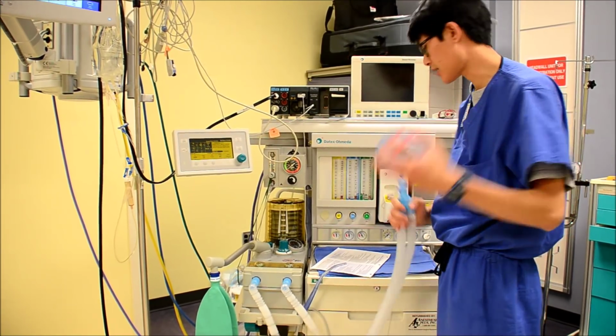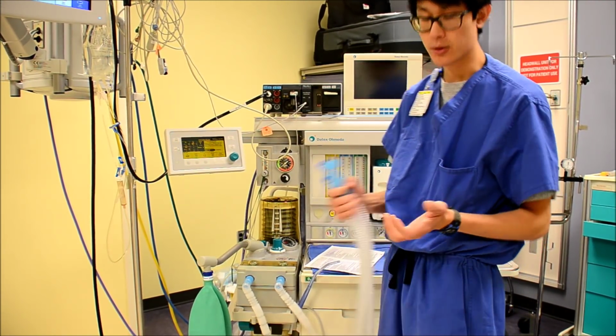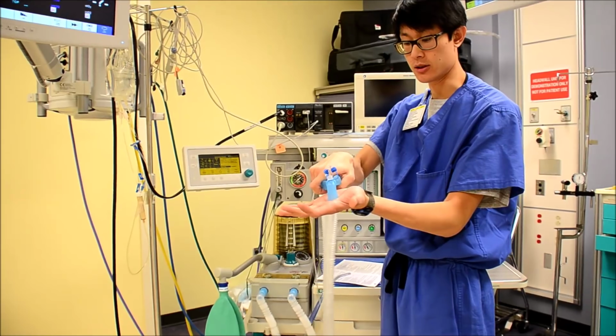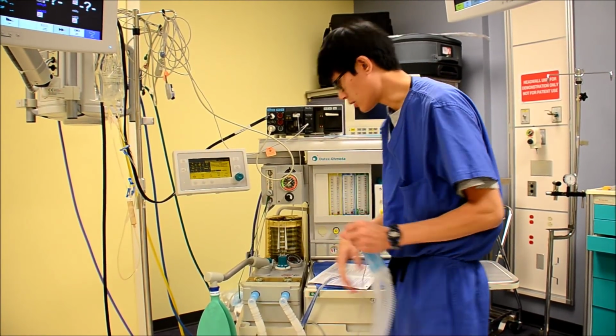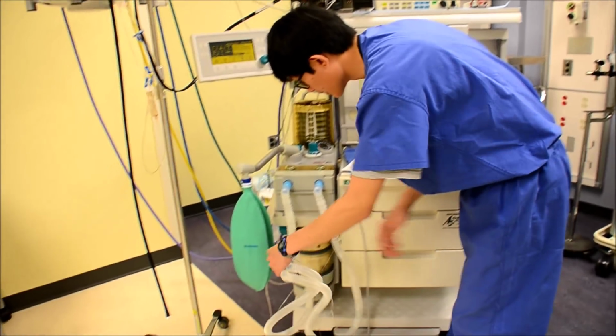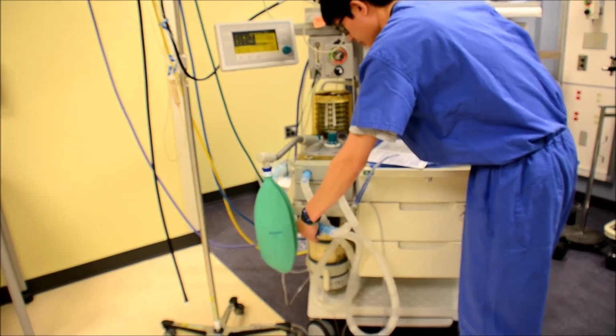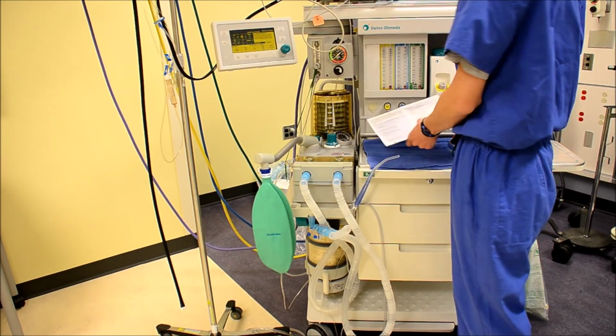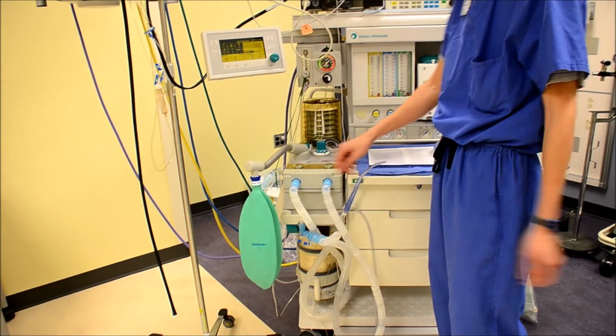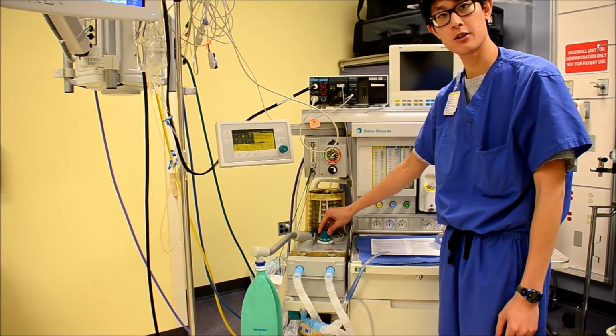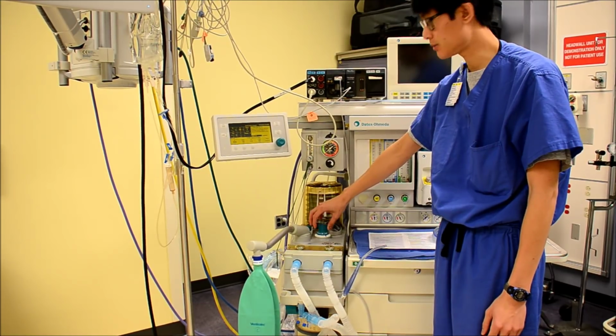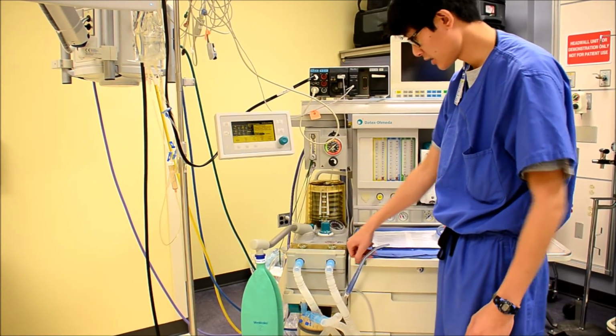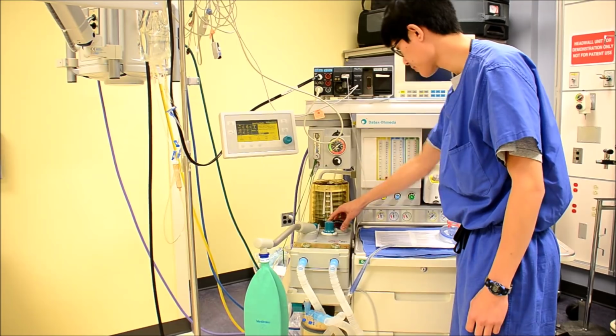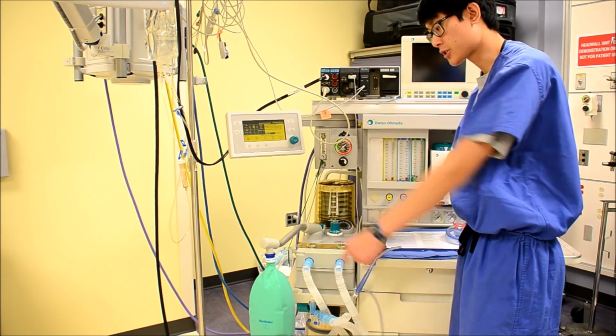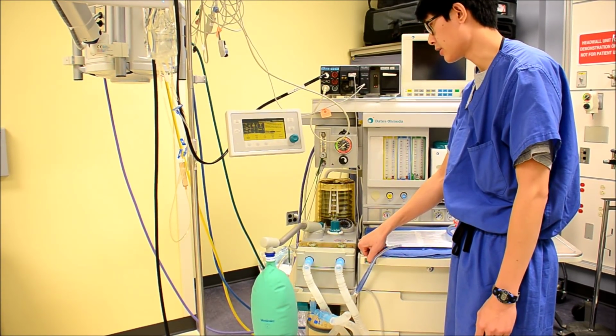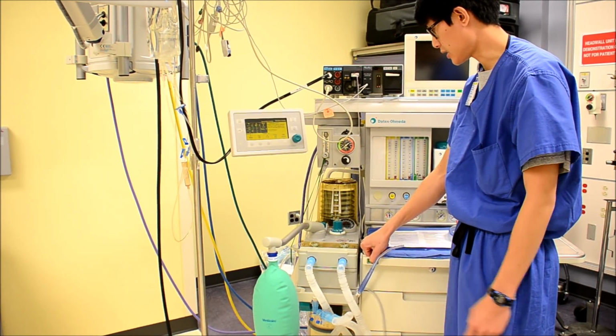You can go ahead and take off your mask. And there's two ways you can do this. You can either hold your hand to occlude the circuit, or there's a little plug here. You just plug it right there so your hand's free. So we want to make sure our scavenging system's working. So everything's occluded. The APL valve is set to open at minimum. You go ahead and flush your system. You'll see your circuit bag fill, and you should hear the waste gas come off on the other side.